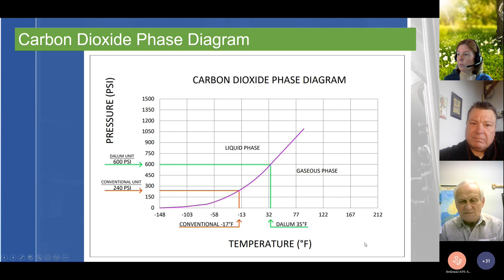Now, the reason we did that is because with a conventional system, when you go to 240 psi, breweries do not have refrigeration to get down that low. Normally, your glycol system is 25 to 35 degrees, somewhere in there, whatever you need to maintain your fermenter temperatures. So a conventional system will require an additional refrigeration unit attached to it or somewhere in the brewery to get down to minus 17 F. With our system, we tap into your house glycol system. In other words, the same cooling system you're using for chilling fermenters or making chilled water or whatever. So that's really the difference between the conventional technology versus what we call the Dalum unit technology. The compressor was developed again by Kim Dalem. It's a proprietary compressor, 3-stage, and we'll talk about that in just a minute. Next slide.